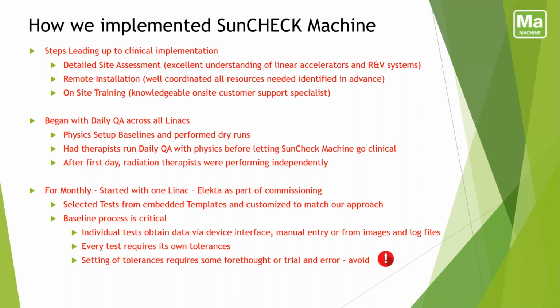And for the monthly, we started off with the Elekta Linear Accelerator, which was a new installation as part of the commissioning. We selected tests from the embedded templates and customized them to match our approach. And the baseline process turns out to be critical.